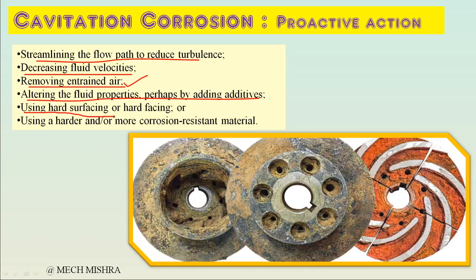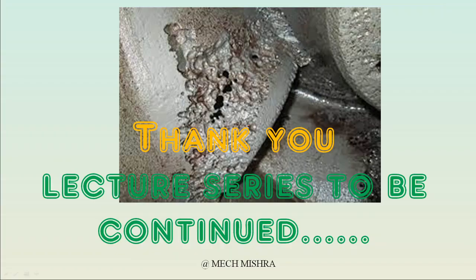Using hard facing is an upgrade. You can hard face or hard surface your pump parts, piping parts or tubing parts to make them cavitation resistant, or use a harder and corrosion resistant material. You can upgrade the material directly. So these are the actions you can take proactively to avoid cavitation. So friends, we have learned that cavitation is not only a problem in pumps, it's also in exchangers, piping, venturis and downstream piping where there is turbulence.